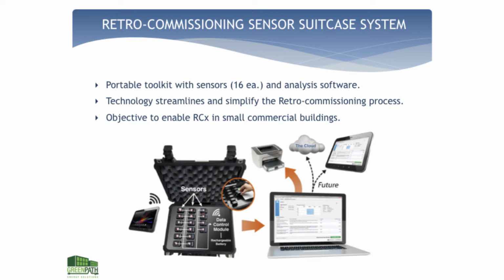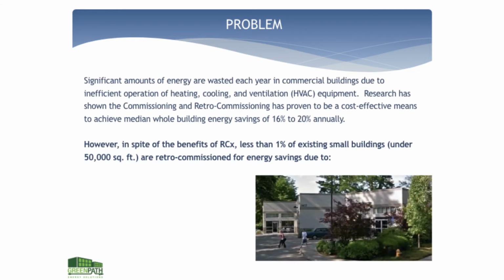The objective of the suitcase is to enable retro commissioning in small buildings and to realize approximately 10% whole building savings while reducing implementation costs, so that servicing this sector is cost-effective with an acceptable return on investment. Significant amounts of energy are wasted each year in commercial buildings due to inefficient operation of heating, cooling, and ventilation (HVAC) equipment. Research has shown commissioning and retro commissioning to be a cost-effective means to achieve median whole building energy savings of 16 to 20% annually.